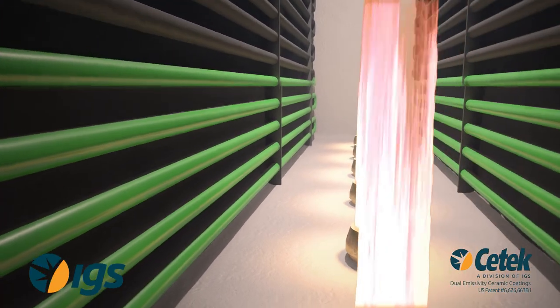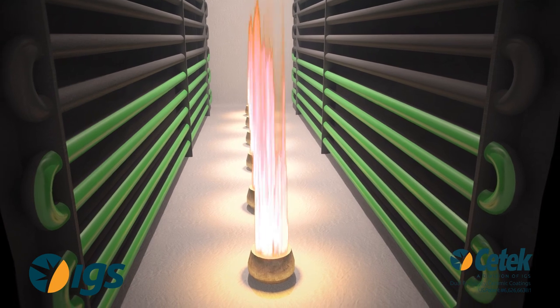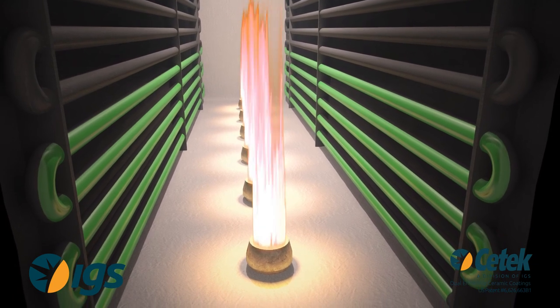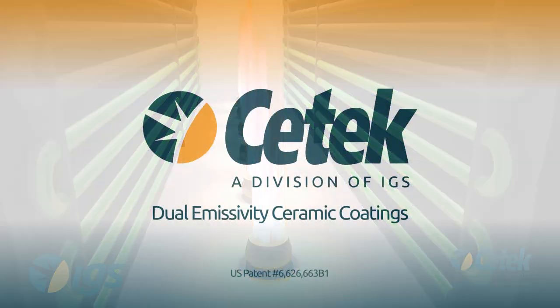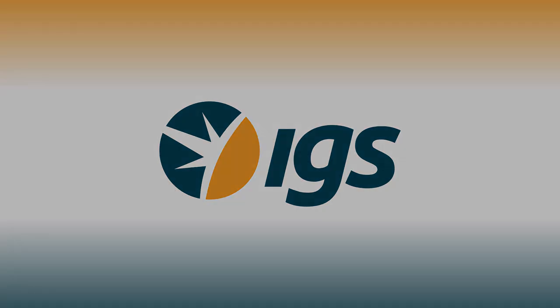This prevents rapid coke formation, while at the same time eliminates uneven scale formation, allowing accurate tube metal temperature measurements. With improved heat uniformity, Cetek ceramic coatings can increase run length and improve radiant efficiency.